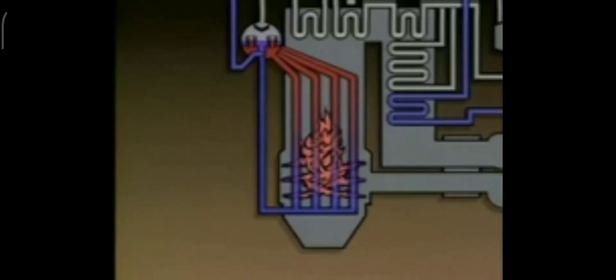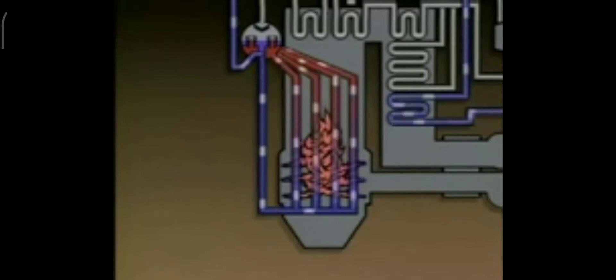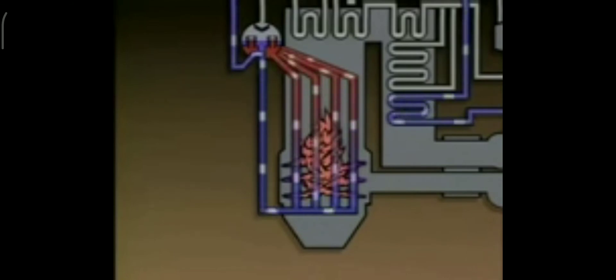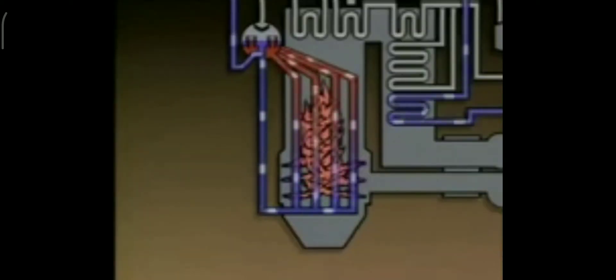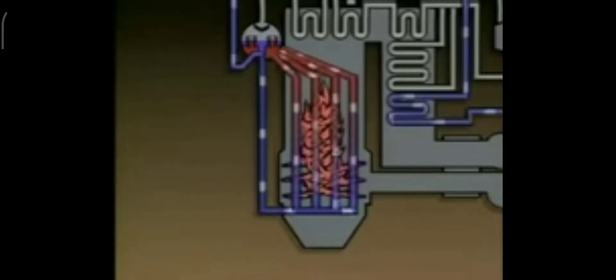The water walls are heated by the burning fuel in the boiler furnace. As the mixture of water and steam rises, cooler water from the downcomers flows into the lower headers and then into the water walls. The cooler water is also heated and rises, creating a self-sustaining flow through the water side of the boiler. Natural circulation of water in a boiler is affected by two factors. Raising the temperature in the boiler furnace increases natural water circulation, because it results in a greater temperature difference between the water walls and the downcomers.